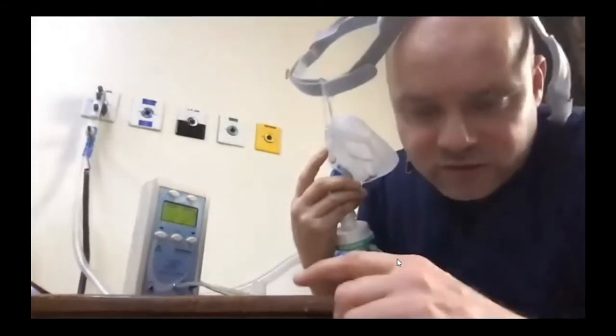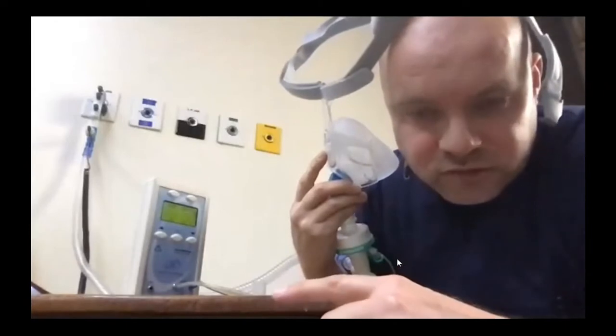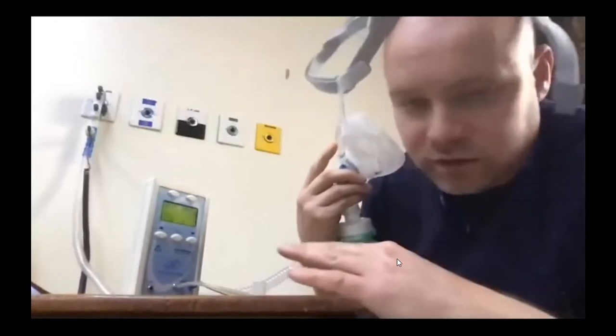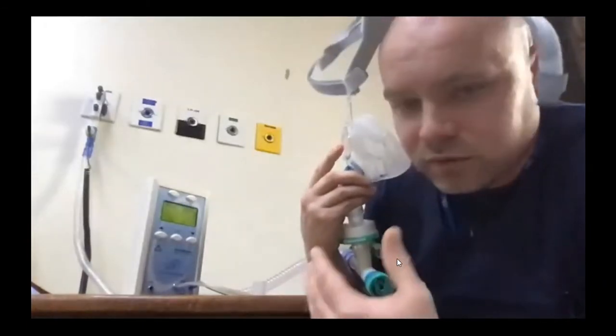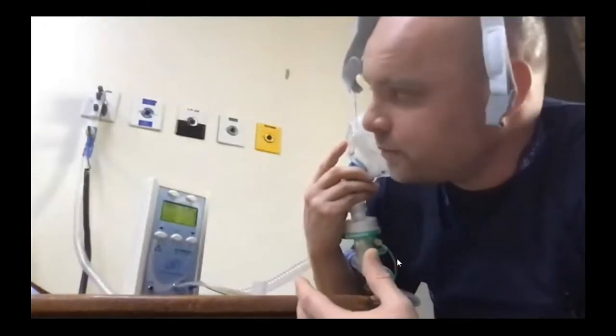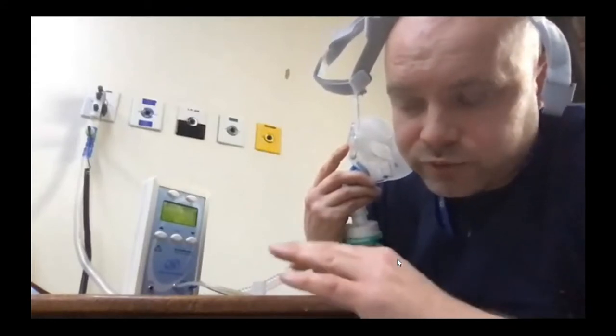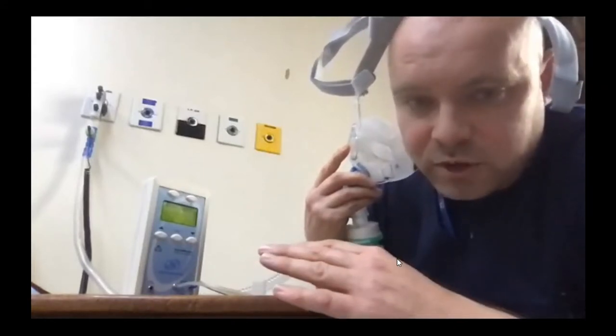So the first setting I've done is I've opened it through one 360-degree turn. What you'll find there, the flow that you're getting is a little bit under 20 liters per minute. Obviously, it's a little bit harder to breathe because the vast majority of the air is now being entrained. And the FiO2 that I'm getting sits at around 30% to start with. The lower your flow rate is, it does tend to climb over time at the very low limits.